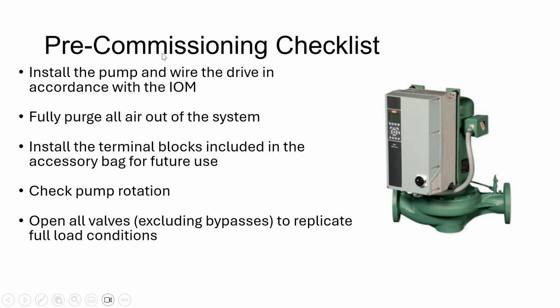Where am I going? All right, so here's a very important slide, another very important slide, pre-commissioning checklist, okay? Before you start starting this up, our technical service team makes sure or demands that this is done first, right? So install the pump and wire the drive in accordance with the IOM, right? So boom, first you got to do that. Pretty straightforward. That shouldn't be hard to do. Fully purge all air out of the system, right?